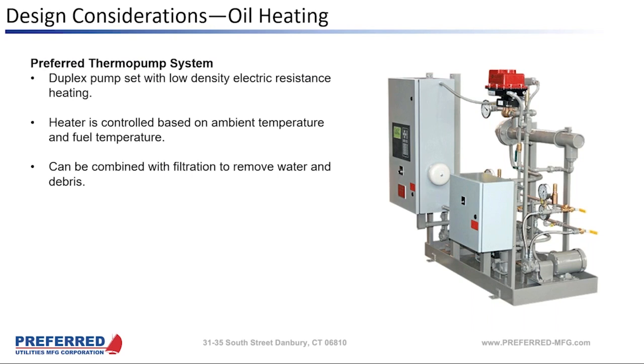So I did a bunch of these in Dallas at data centers around DFW. There's a lot of corporate headquarters here and a lot of small data centers, and they wrote us some logic so that when the Thermopump was commanded to come on by cold ambient air temperature, it also commanded return pumps to come on, one belly tank at a time, and pump the belly tank down to the supply pump on level, which is 50% full. And then we would top off each day tank one at a time with fuel that came out of the Thermopump.